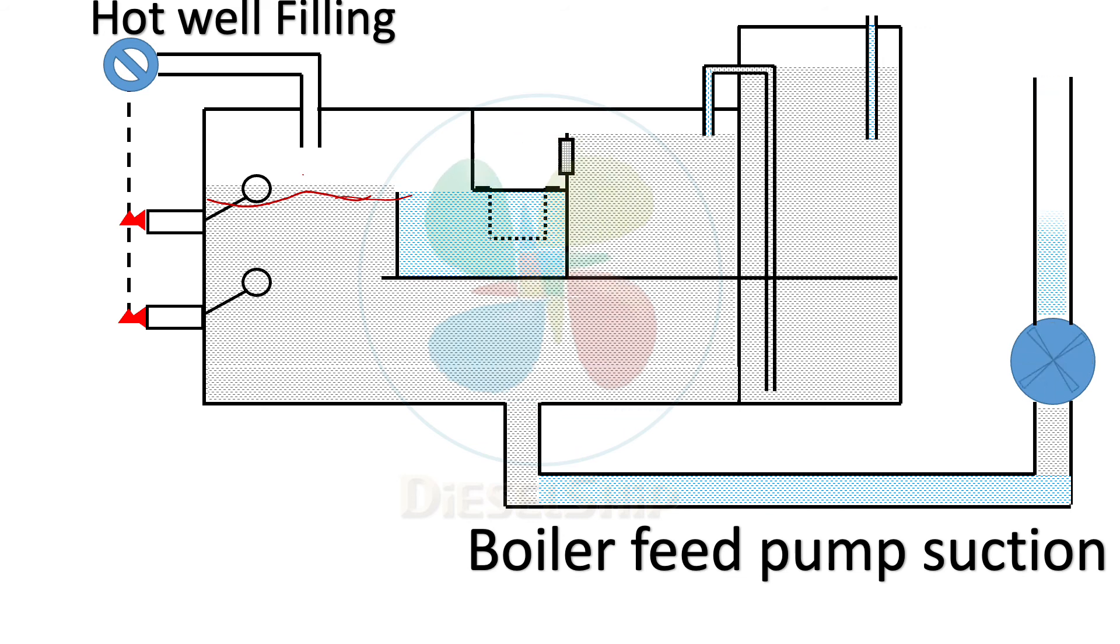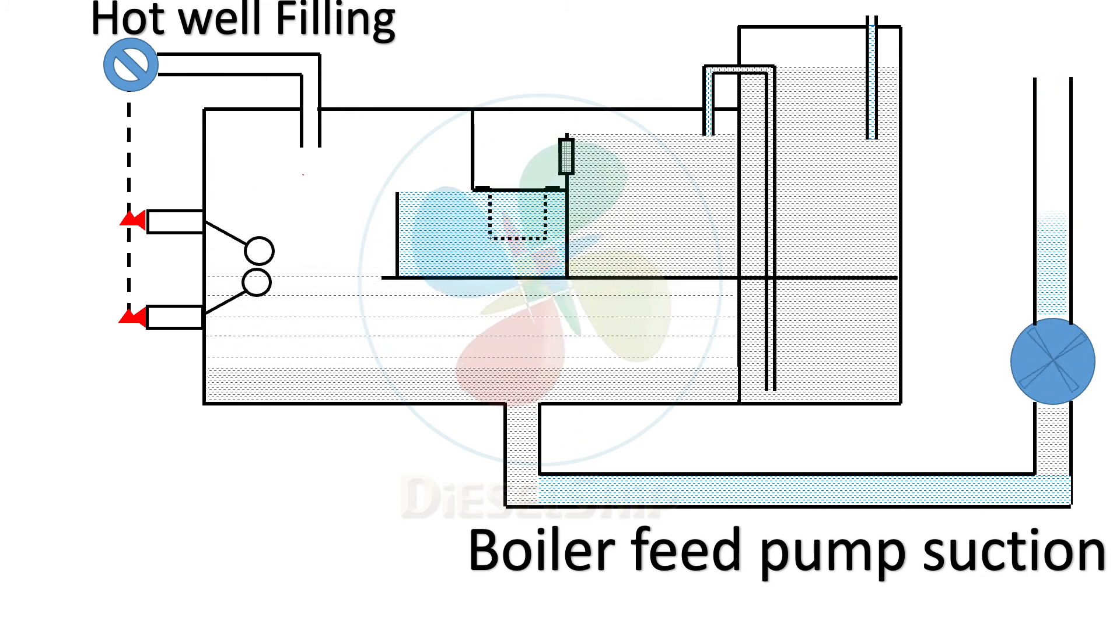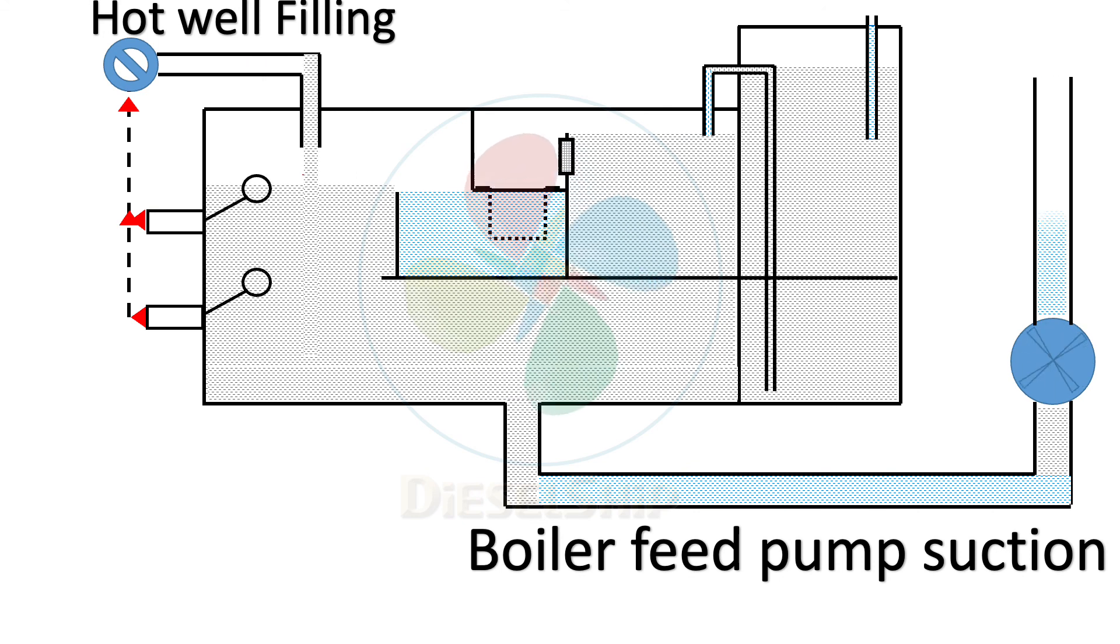Let me simulate the water level dropping. The float drops down and triggers the hot well filling valve to open. The hot well filling starts to fill up. Now the level starts coming up to this safe level. And now the float will tell the hot well filling to stop filling. The significance of why I showed you this filling separately is that you should always remember the level has to be maintained only till here. This is usually asked in your exams, competency exams, be it class 4 or class 2 or even class 1.